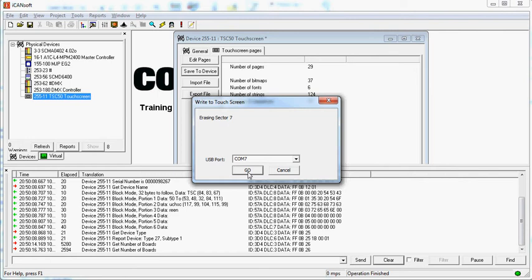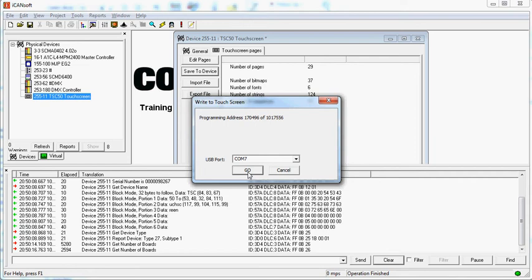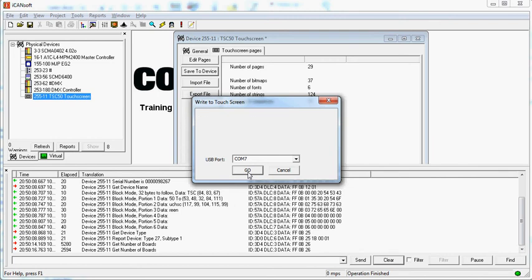And the good sign is that we're getting this erasing sectors. And it's going to wander through all of these and then it's going to do the downloading. As I said, make sure you've disconnected the data, especially if you've got a network which has got traffic on it. Otherwise you'll find this stops and starts, timeouts and whatever. It would eventually get there, which is just frustrating waiting for it to actually happen. So we've got to wait for this to go right the way through. It will eventually get to the end and just say touch screen programmed. With the TSC 50 you have to disconnect the power and wait a couple of seconds and then reconnect it.